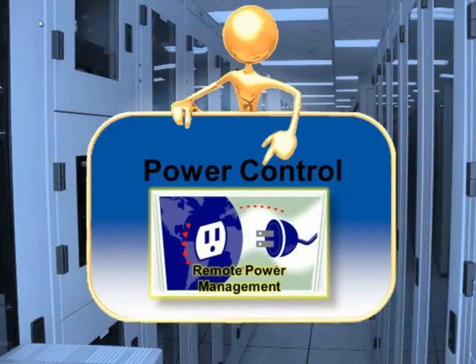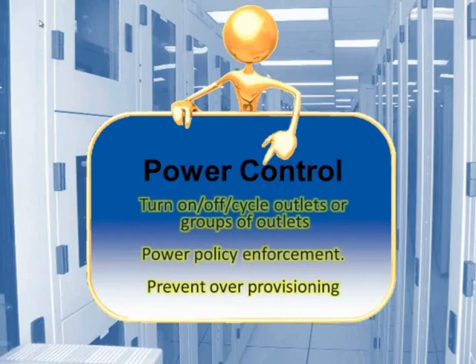Besides monitoring power consumption, some rack PDUs allow for remote power management. Would you like to be able to reboot stuck servers without having to visit the data center? Power outlet cycling is ideal for data centers without 24-hour staff coverage or devices deployed in remote locations, such as a wiring closet or off-site hosting. The ability to schedule power off per outlet allows you to easily enforce IT power policies, such as requiring that all non-production servers be turned off after 6 p.m.